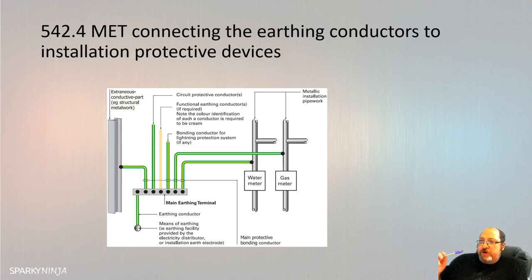But when you go to the larger installations, switch rooms, for example, you'll often notice when you've got all the switchgear in front of you, maybe behind you on the wall or further down in the corner, there'll be a big brass earth bar. And there'll be all these large earths and bonds, but then there'll be a link, like a bolted link, which then goes to the main earthing conductor. And the idea being, just get a simple spanner or whatever, you undo that link, you swing it off, and you've now removed all of the bonding and all the other earthing from that main earthing conductor. So you can then do a test of the earthing conductor without all the parallels.